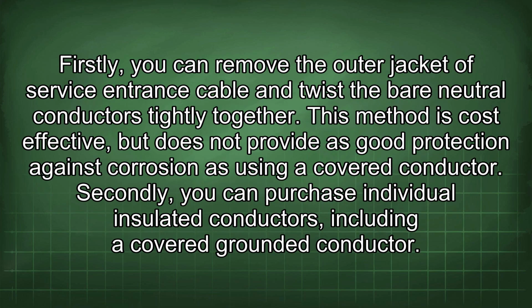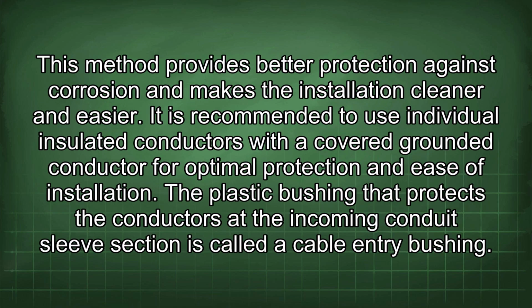Firstly, you can remove the outer jacket of service entrance cable and twist the bare neutral conductors tightly together. This method is cost-effective but does not provide as good protection against corrosion as using a covered conductor. Secondly, you can purchase individual insulated conductors, including a covered grounded conductor. This method provides better protection against corrosion and makes the installation cleaner and easier. It is recommended to use individual insulated conductors with a covered grounded conductor for optimal protection and ease of installation.